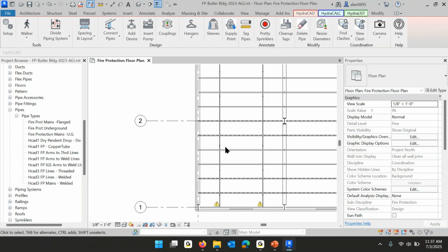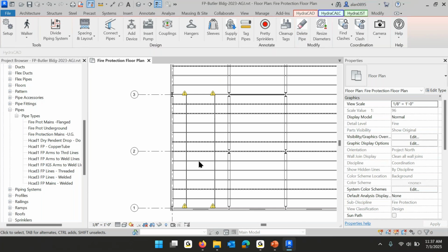And Revit made a law for their tools that says, if an object is parallel to the view that you're in, we will show the symbol associated with it. And that symbol is a foot in diameter. The sprinkler doesn't have a foot in diameter or anything, but it makes it easier to see if you represent it with that 1 foot circle. But if it's not parallel to the floor, like if it's in a section or an elevation view, you don't want to be seeing that extraneous line. So they shut it off.